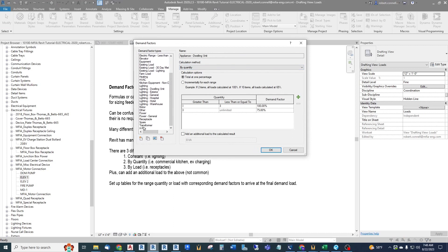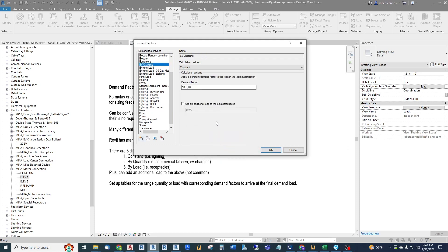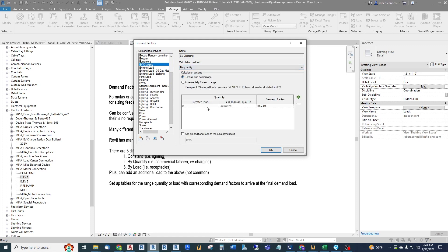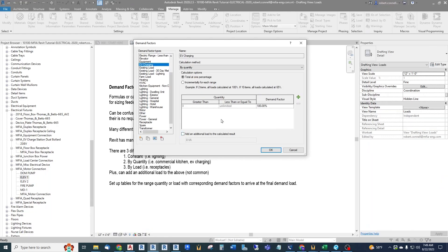The Oregon demand factor table for EV charging is: 1–4 charging points at 100%, 5–8 at 90%, 9–14 at 80%, and it continues stepping down. We'll enter this into a new Revit demand factor. Under Demand Factors, create a new one called 'EV Charging' — or 'EV Charging Oregon' to be more specific. Based on the NEC we'd use 125% for continuous load, but we're applying the Oregon rules, so we select calculation method By Quantity.